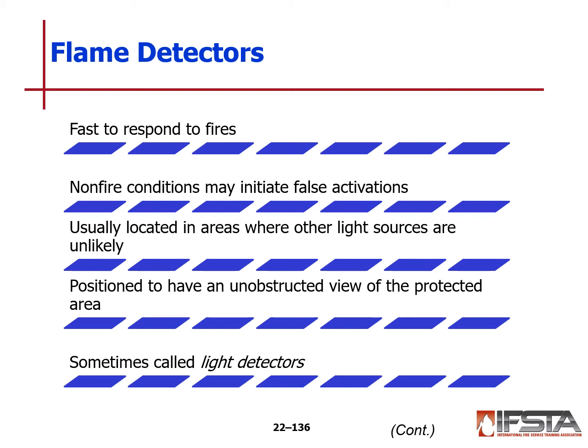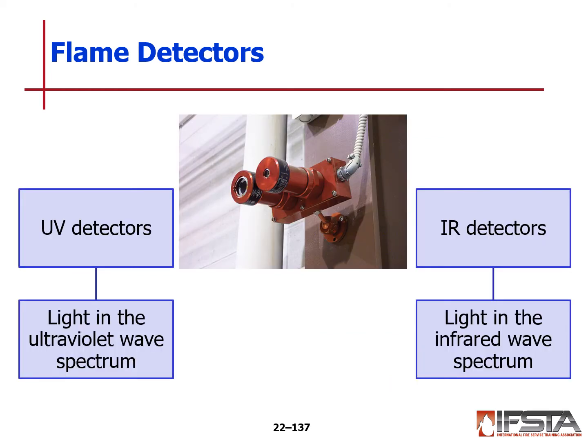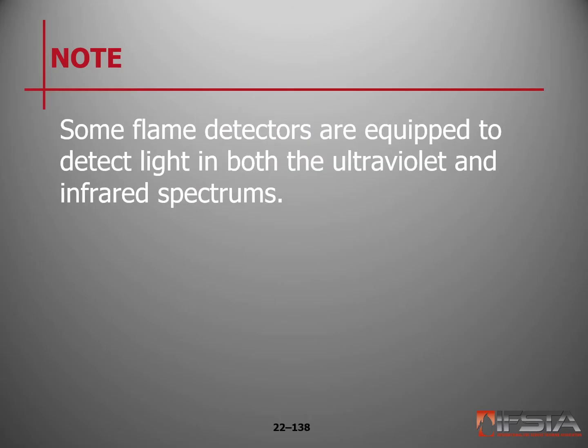Flame detectors are very fast to respond to fires. Non-fire conditions may initiate false activations. However, usually they're located in areas where other light sources are unlikely. Positioned to have an unobstructed view of the protected area, sometimes they're known as or called light detectors. These can be UV detectors, light in the ultraviolet wave spectrum, or infrared detectors, light in the infrared wave spectrum. Some flame detectors are equipped to detect light in both the ultraviolet and the infrared spectrum.